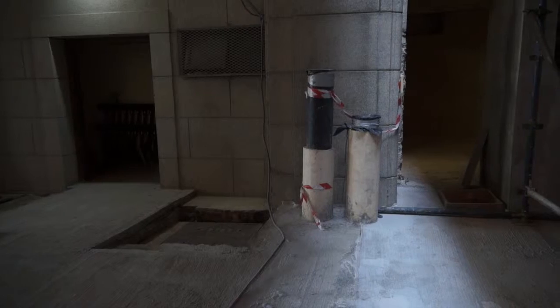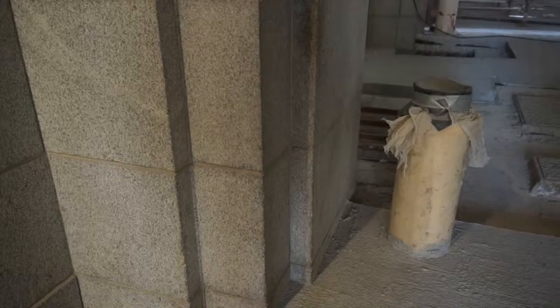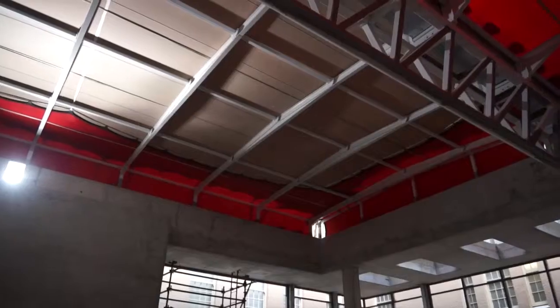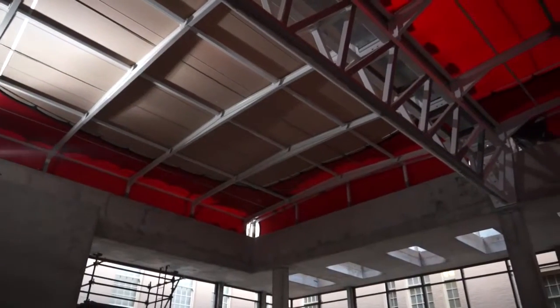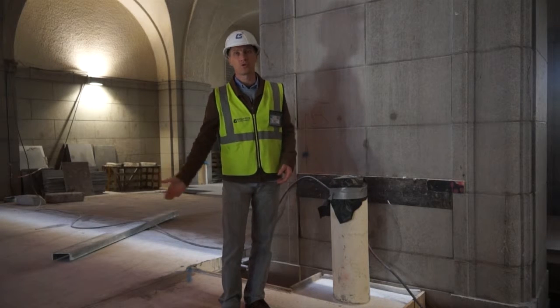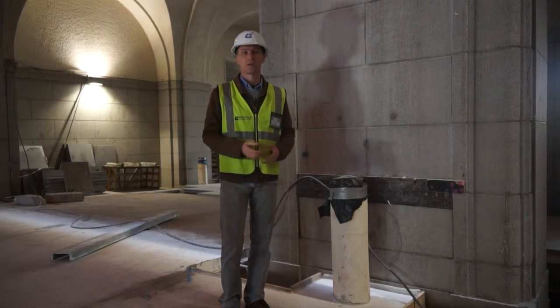So displacement means that we're pushing in our fresh cold air at the low level and pushing out the hot air out of our skylights and our roof vents. And then that complements the floor cooling system, which is our primary heating and cooling element.